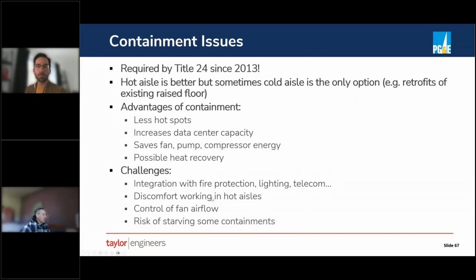And when you do have containment, hot aisles can get pretty hot. So there's issues with people. It doesn't bother the computers to have hot aisles, but it can bother people working in them. You need to think about how you're going to control your airflow, and it actually can introduce some risks because now, because you've sort of separated things out, there's a possibility that some hot aisles or cold aisles won't get the airflow that they need. So it needs to be planned out.